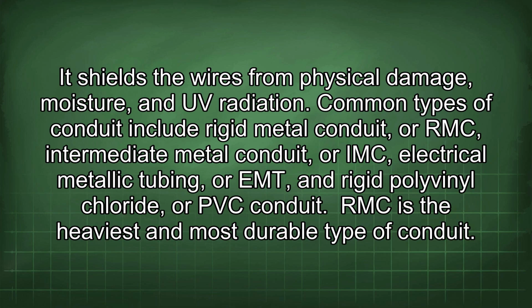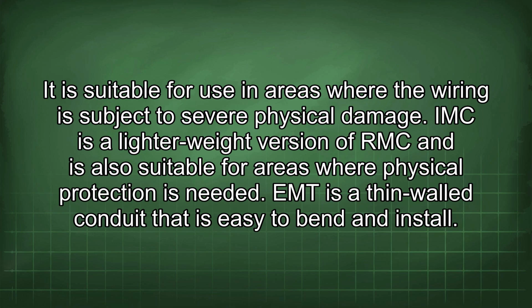Common types of conduit include rigid metal conduit, or RMC, intermediate metal conduit, or IMC, electrical metallic tubing, or EMT, and rigid polyvinyl chloride, or PVC conduit. RMC is the heaviest and most durable type of conduit. It is suitable for use in areas where the wiring is subject to severe physical damage. IMC is a lighter weight version of RMC and is also suitable for areas where physical protection is needed.